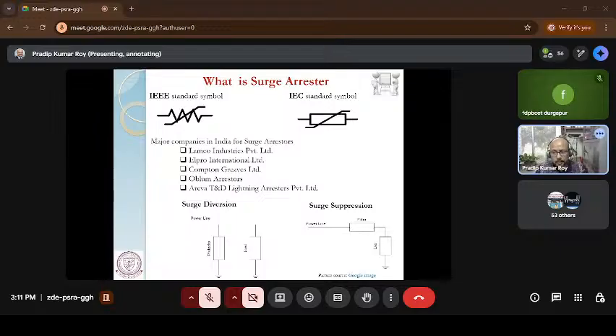But as soon as the surge comes, the surge arrestor immediately converts into a conductor, and all the high voltage passes through that surge arrestor and protects the transformer, the highly costly transformer. So here I am talking about surge diversion. Surge arrestor is mainly used for surge diversion, not surge suppression. In suppression, we normally connect it in series, not in parallel. So I'm not talking about surge suppression, I'm talking about surge diversion.